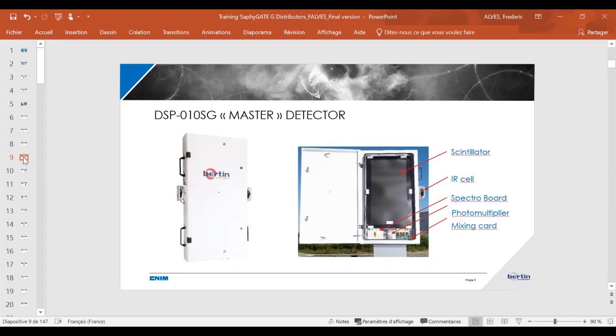Concerning the master detector, it is presented like that. The master detector is easily identified thanks to its 2 infrared cells. You have infrared cells on each side of this detector. And inside the detector, you have, of course, the scintillator and the photomultiplier. On the left side you have the spectro board, and on the right side you have the mixing card.